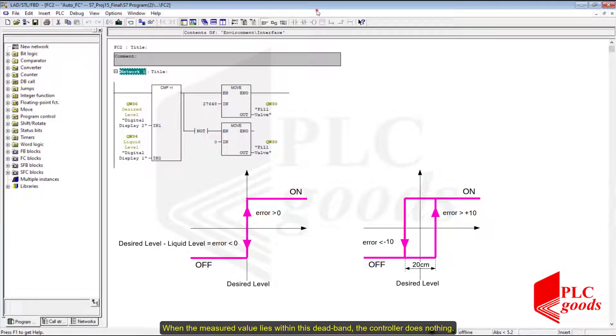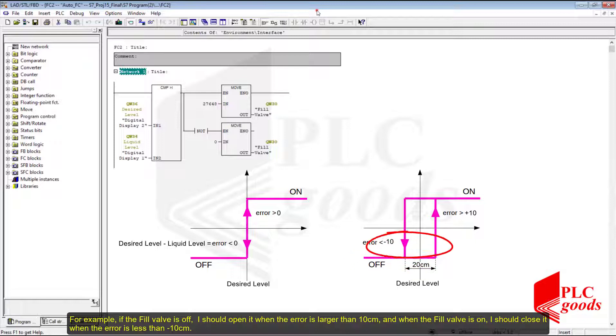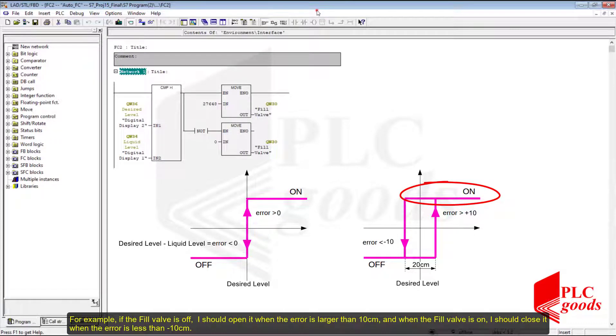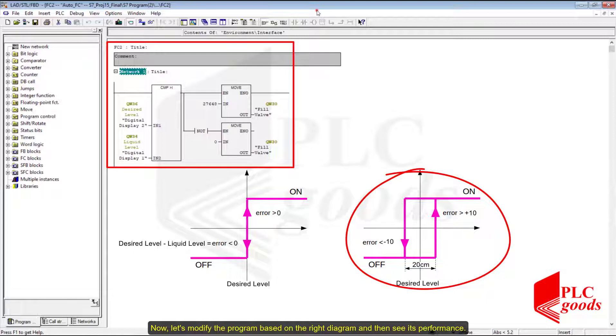When the measured value lies within this dead band, the controller does nothing. For example, if the fill valve is off, I should open it when the error is larger than 10 cm. And when the fill valve is on, I should close it when the error is less than minus 10 cm. Now let's modify the program based on this diagram and then see its performance.